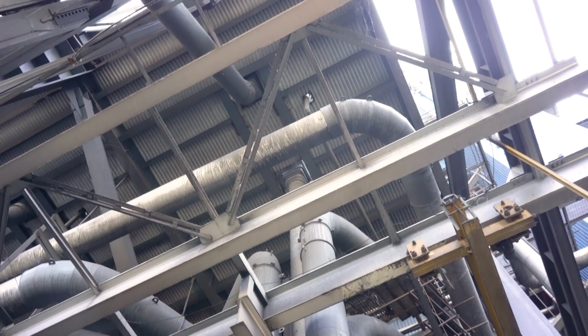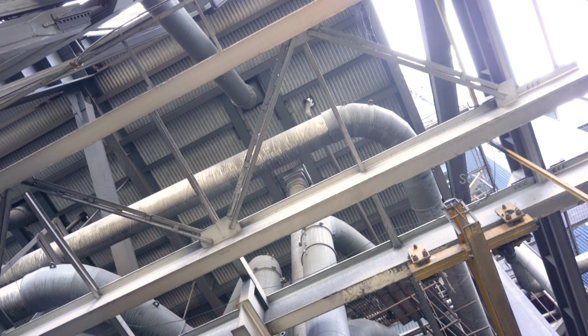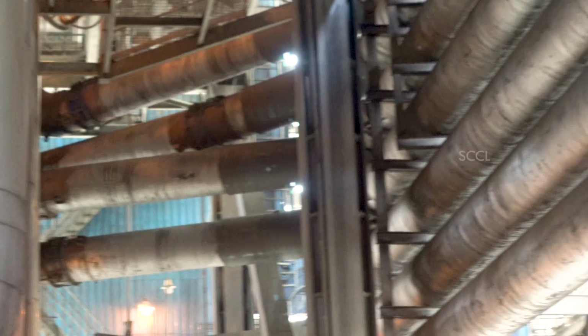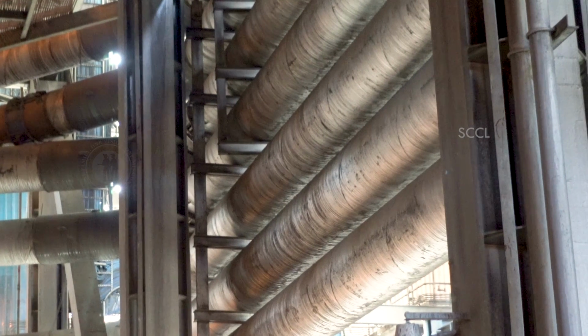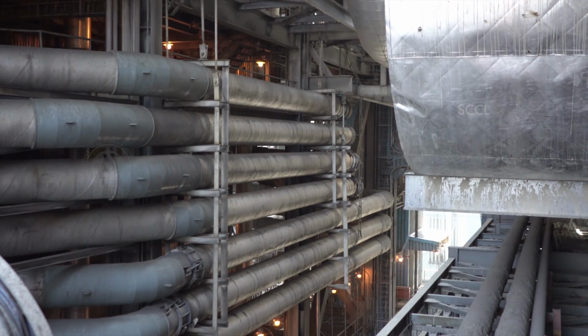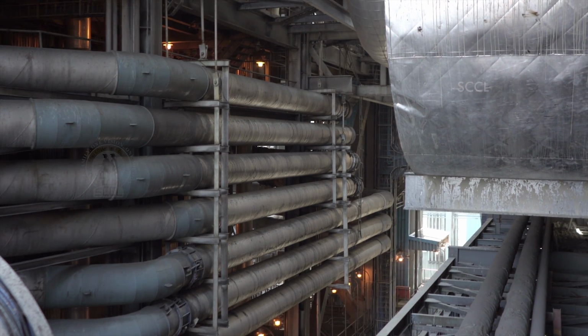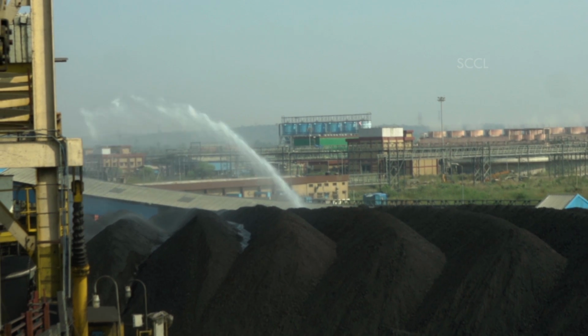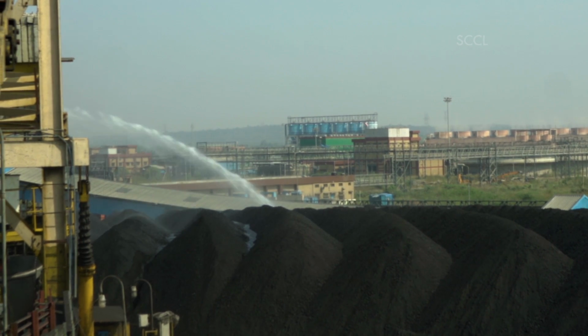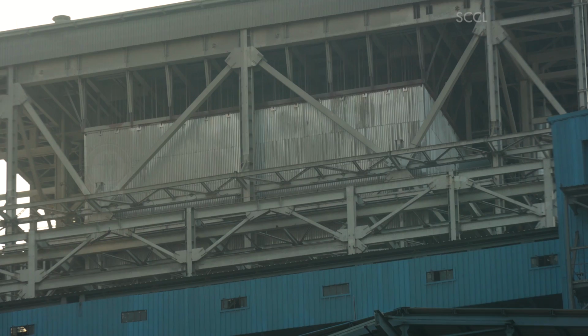Atmospheric air is preheated and becomes warm air. This air sucks the pulverized coal from the ball mill and supplies to the boiler through the burner. The purpose of air heating is to remove the moisture content in the pulverized coal and thereby improving the boiler efficiency.